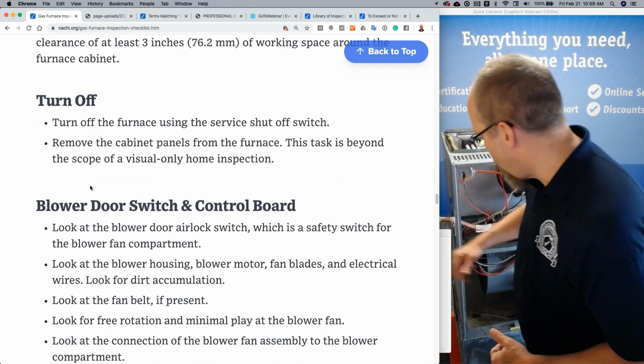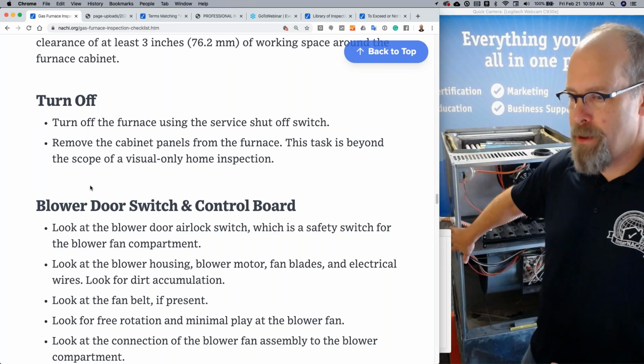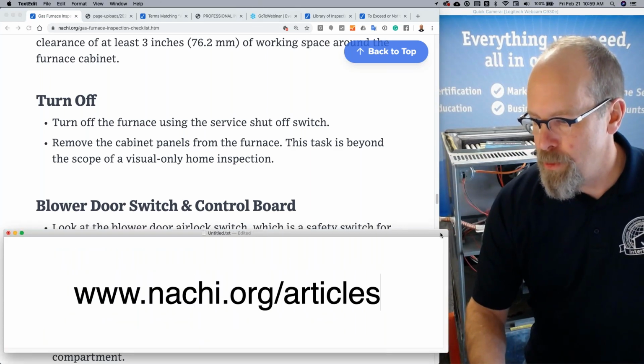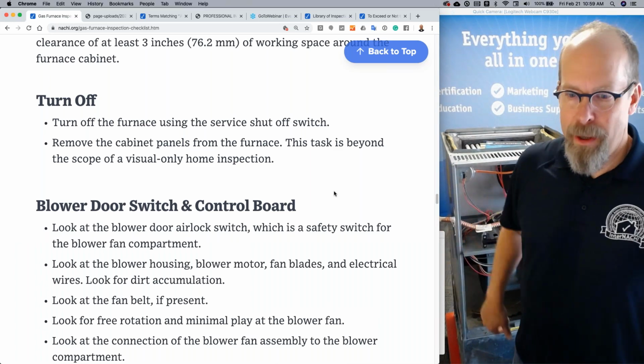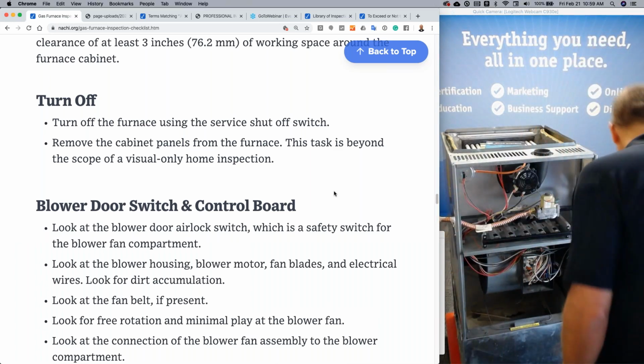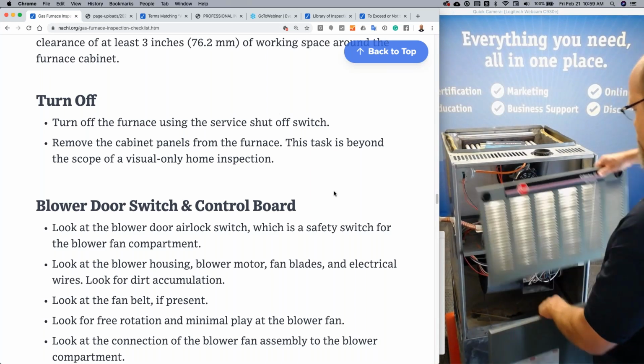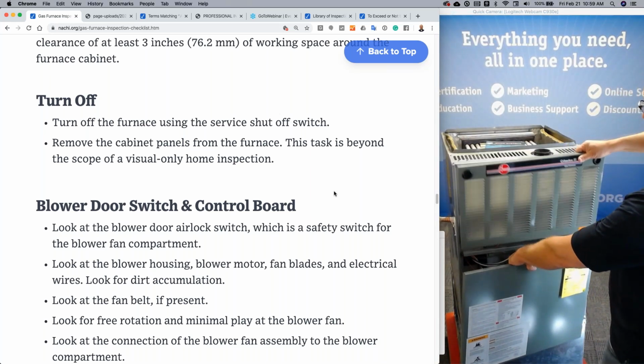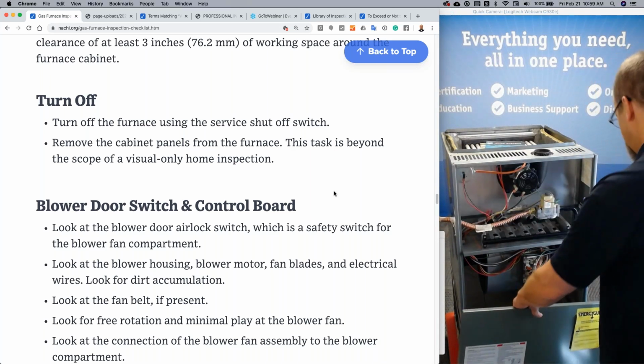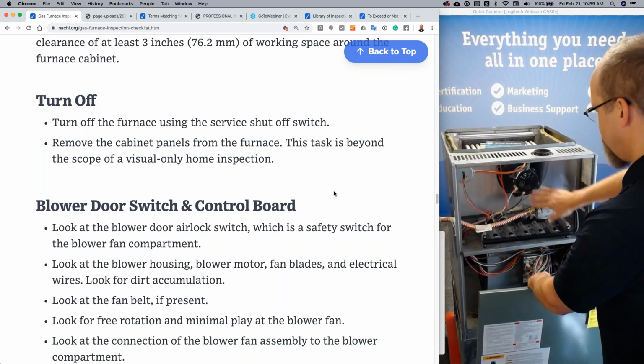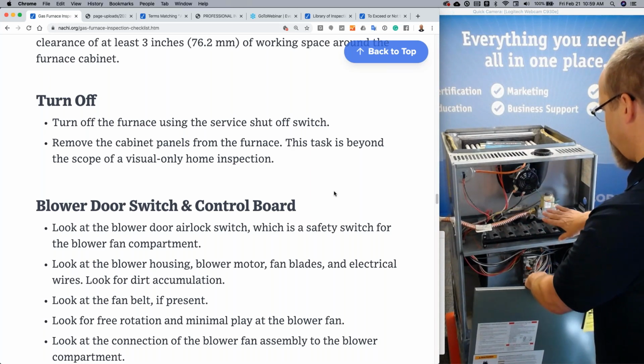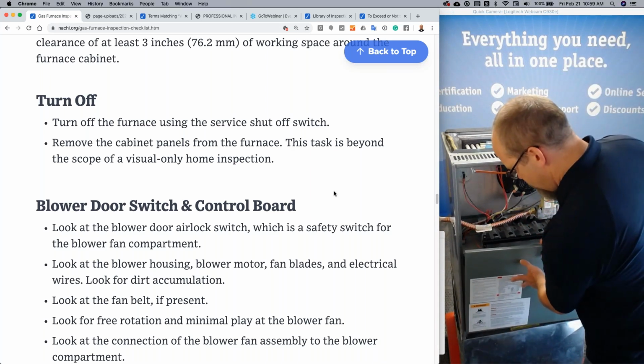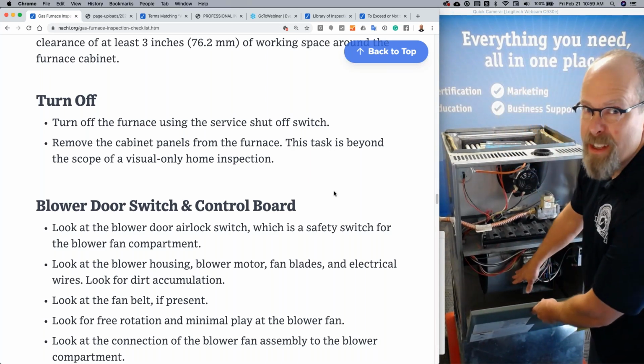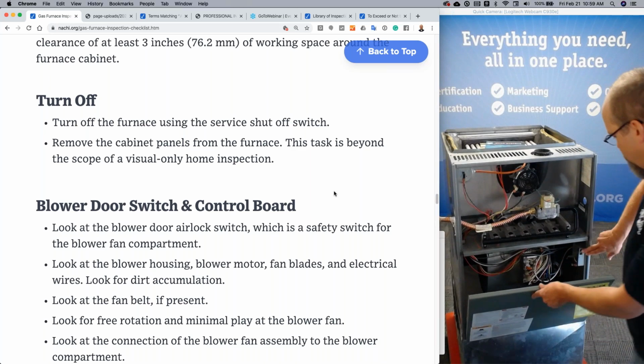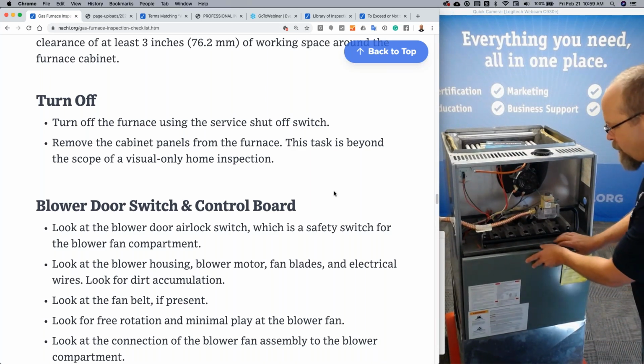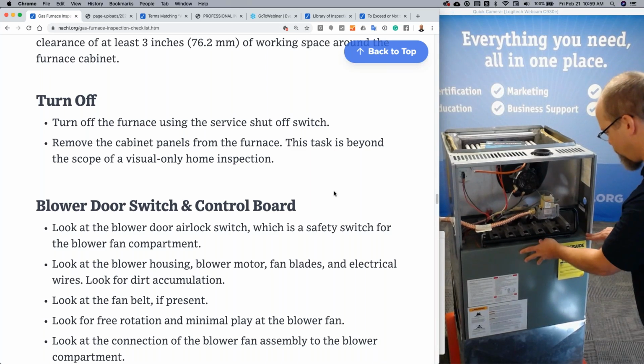So you can turn off the unit. This system doesn't have a switch on the side, but you can turn off the system if you wanted to and turn it back on. You can turn off the unit and then remove the panels. The burner compartment door, they call it a door or a panel front, gets you to the draft inducer and the switches and the manifold and the gas valve and the burners. And this one is to access the blower, obviously. Sometimes the air filter is here, and the emergency shut-off switch or the blower compartment air lock switch is right there. It's missing on this unit.